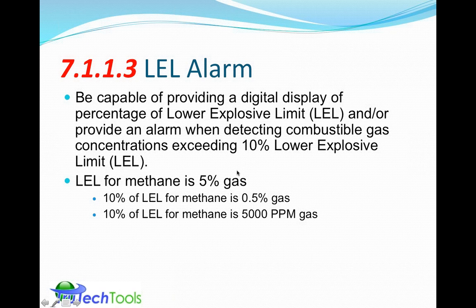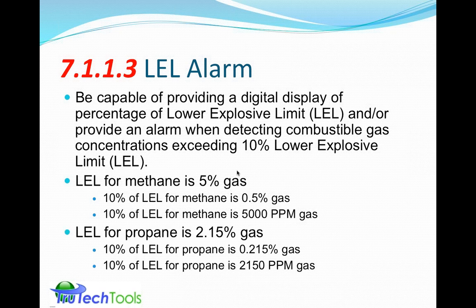Just to give you information, the lower explosive limit is specific to the type of fuel gas that you have. Propane or methane are the two most typical types. So you can't really say a percentage of gas, because the lower explosive limit for propane is 2150 ppm. 10% of the lower explosive limit for propane is 2.15% gas, and 10% of the lower explosive limit for methane is 5000 ppm. So that's why it's stated in lower explosive limit.